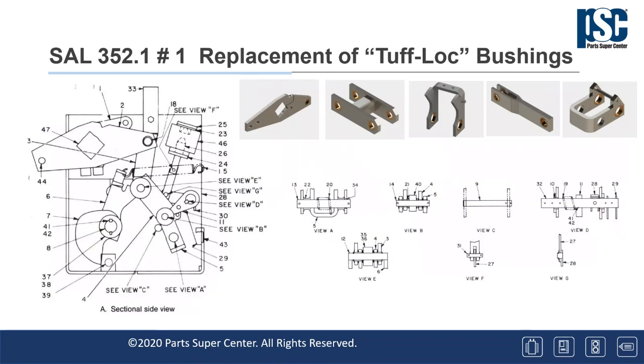Next is number 1, also on SAL 352, which replaces the Tuff-Loc mechanical bushings with superior bronze bushings. Tuff-Loc is a Teflon impregnated fiberglass that was white in color. It was intended to be a maintenance-free mechanical bushing. Although they passed the original design life testing, operational experience proved that environmental contamination caused wear and poor performance.